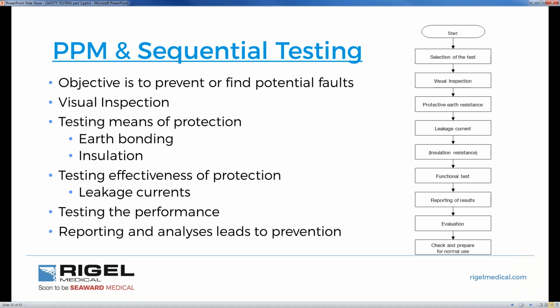We have the testing of the performance of a device, and we also have reporting and analysis that could lead to prevention. So this is the sequential order of your PPM, where we would have a visual test, we do a protective earth resistance, we do a leakage current. We could optionally do an insulation resistance test. We do a functional test, which actually measures the functional current of the device. This is a power reading, how much wattage your medical device actually draws to operate. Then we have the reporting of the results, and we have the evaluation of the results. And that's something that we'll go into later.